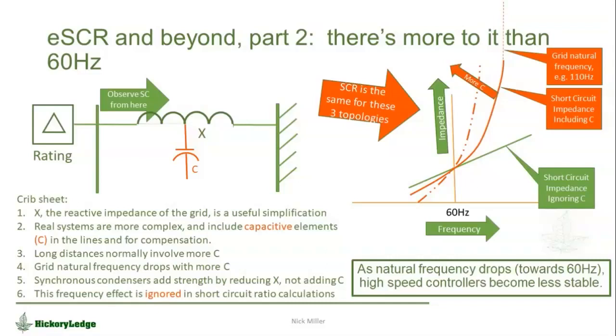But the reality, particularly in power systems that are big and long, where just for the sake of discussion, we might be exporting power from a remote area, the Dakotas, to load centers in Chicago or something equivalent to that. Those long systems tend to be compensated and they have capacitance. So I've made it simple and equivalent on my left by adding the capacitor bank, and you get the idea, right? As the system gets more complicated, it has natural frequencies, and the solid orange line on the right is more representative of a system that's compensated or has charging, and that is that it's not a straight line. It ends up with a natural frequency.